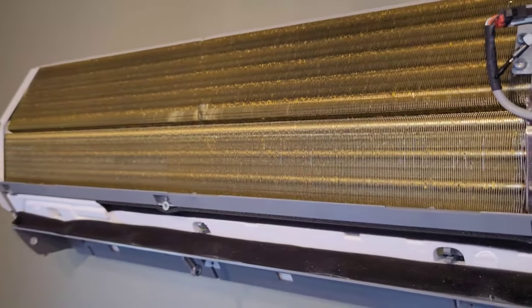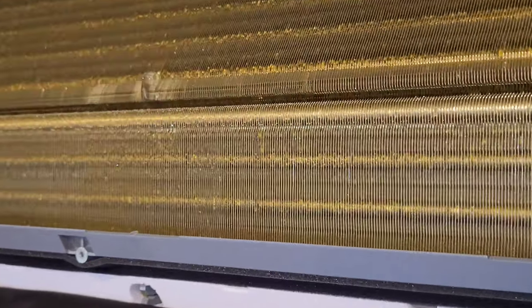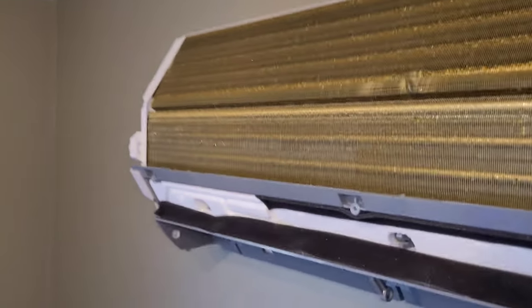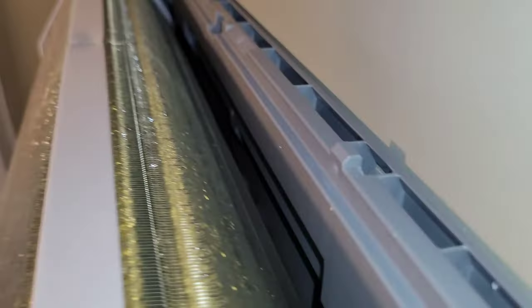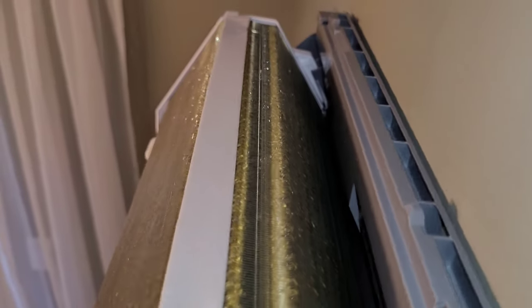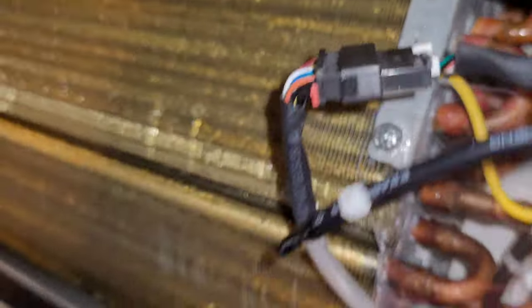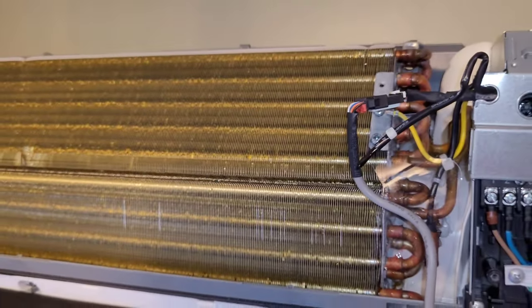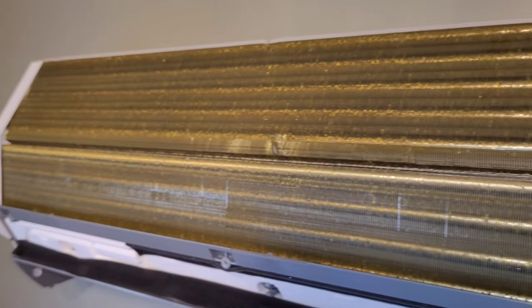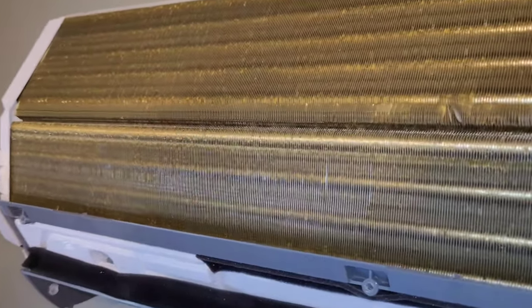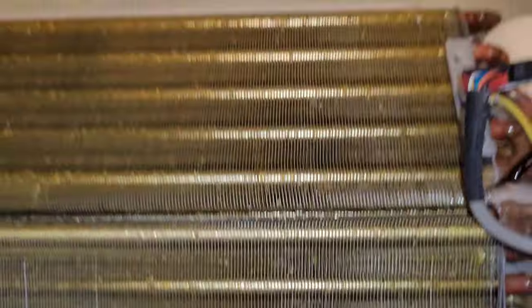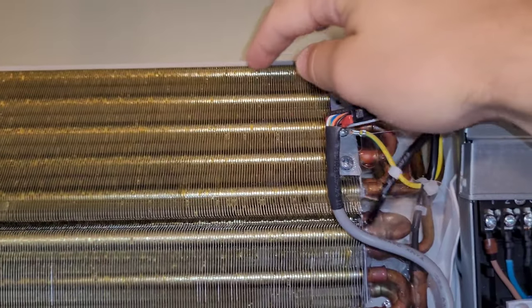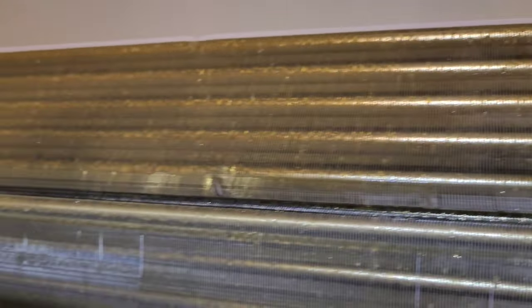Now at this point, you can take a really good look at your indoor coil. You want to check the top and the back as well as the front. Mine's in really good shape, so I don't need to do anything at the moment. But if yours is dirty, you want to start with a dry brush kit. I'll put a link below to an Amazon one, or you can use a simple paintbrush if you have one. You just want to work down the face of the coil really gently, not making any side-to-side movements to damage the fins. You could also use coil cleaner. It'll just run down the face into the pan. But at this point, you shouldn't need coil cleaner.